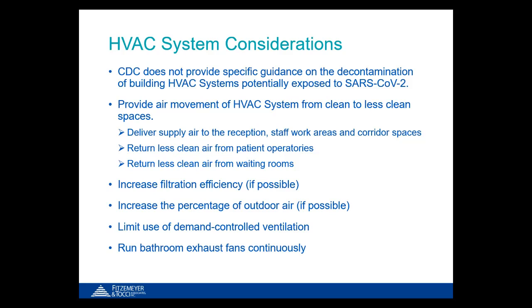They want you to increase the filtration on the central system to as high as possible without negatively affecting the airflow or capacity of the system. The higher the filter efficiency, obviously the more restrictive the filter will be, which could impact the airflow supplied to the space. Unfortunately, many dentist offices that I visited have light commercial or even residential style HVAC systems that simply cannot overcome a high efficiency MERV 13 filter. It would restrict the supply air to the space to a point where it would start affecting heating and cooling capacities of the space. So you've got to be careful of that.